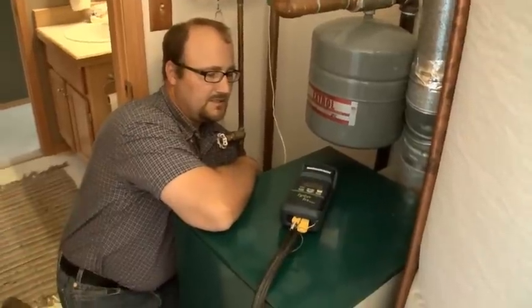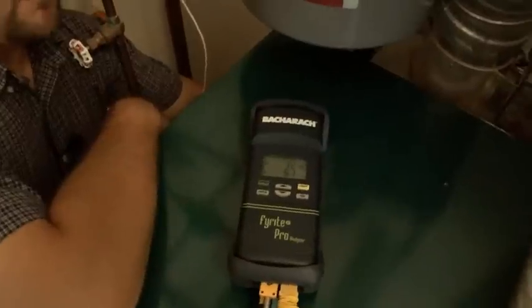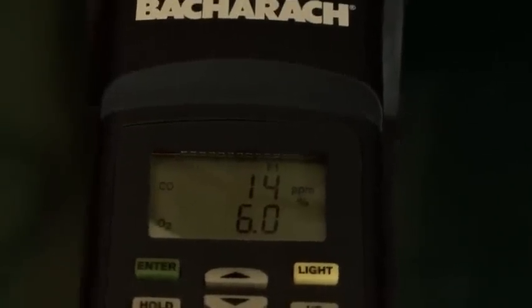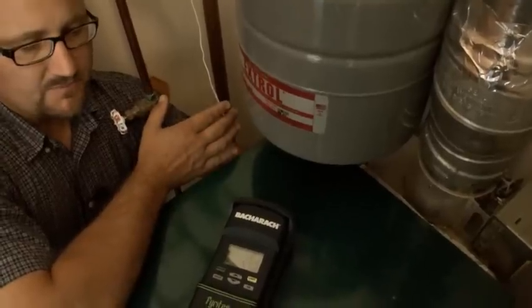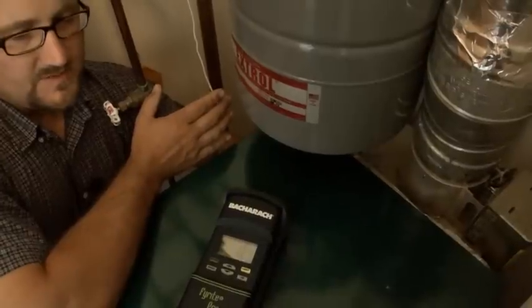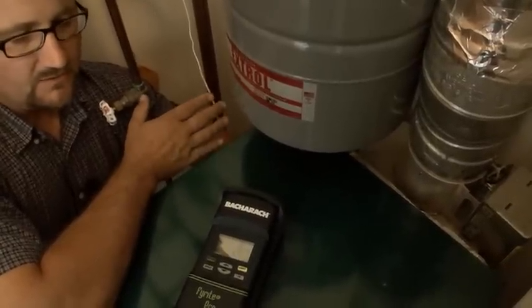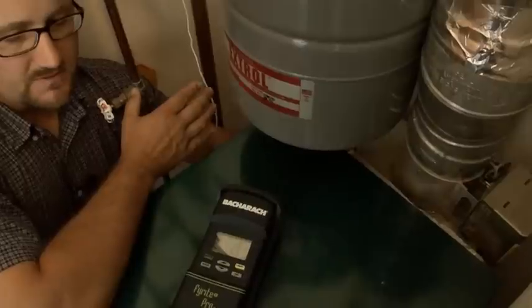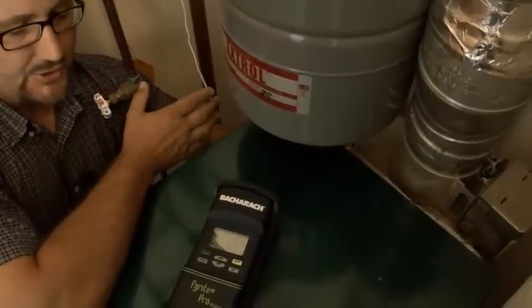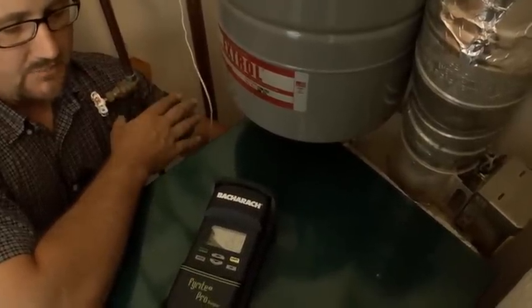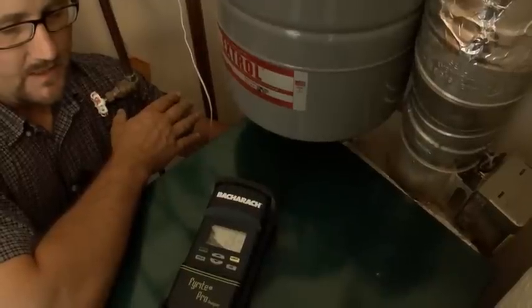We can see our CO. It's climbing a little bit. We'll see what it does as the thing stabilizes. We want to be under 100 parts per million. At 100 parts per million, to get it down to 25, we got to do a little work usually. Typically it's a gas pressure adjustment, possibly an orifice adjustment.